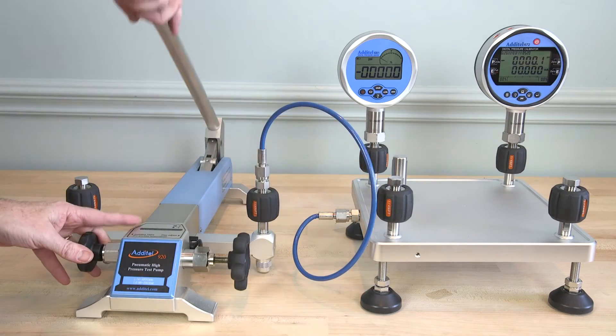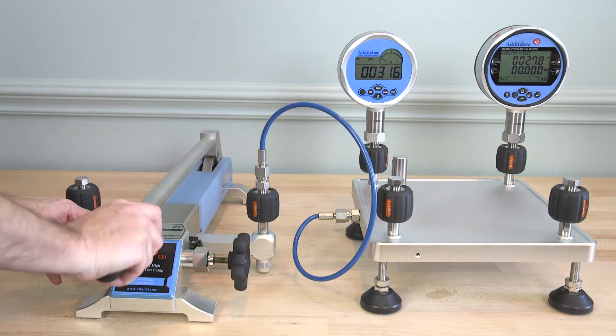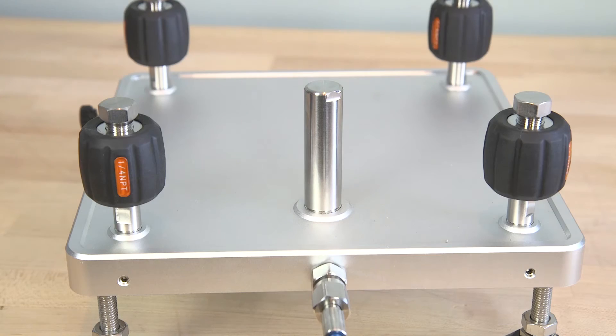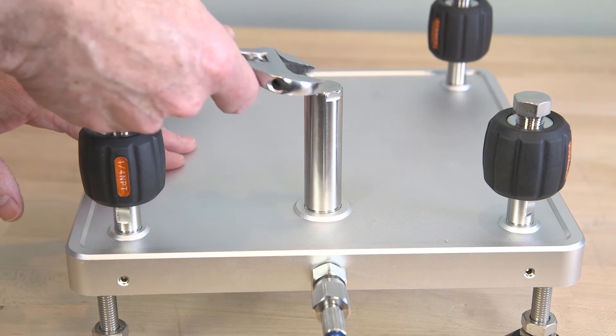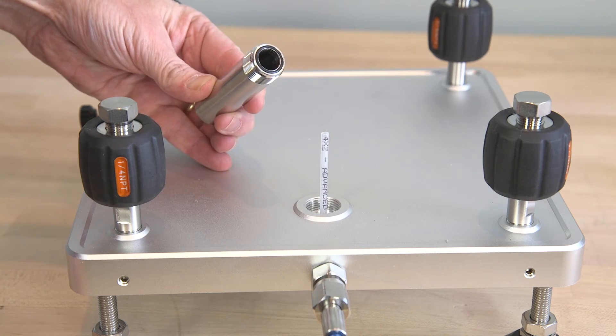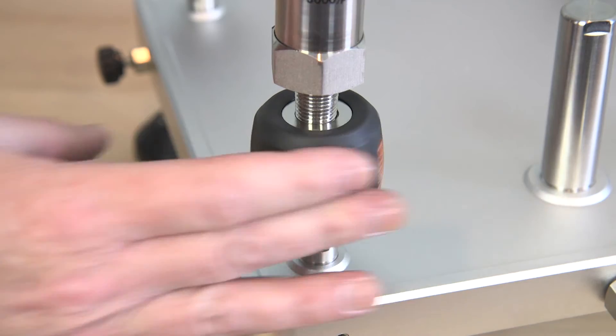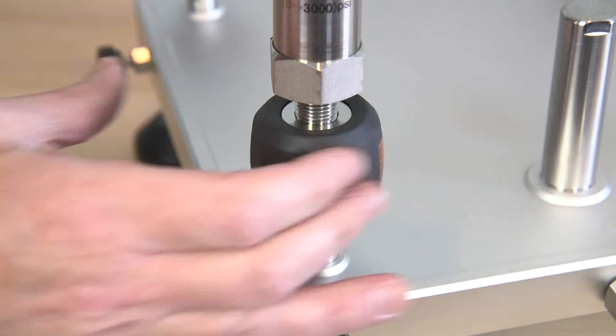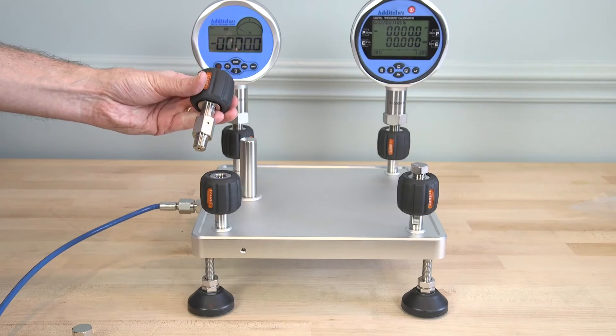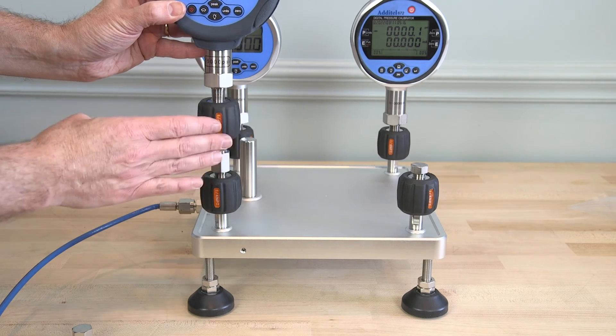The Additel 123 manifold is compatible with hydraulic pressure applications up to 15,000 PSI or 1,000 bar. A filter is built in with the 121 pneumatic pressure manifold to prevent contamination introduced by devices under test. There are four hand-tight quick connectors pre-installed on each manifold, and customers can select from NPT, BSP, or metric threads. 102 and 103 series adapters can be used to connect to other thread types and sizes.